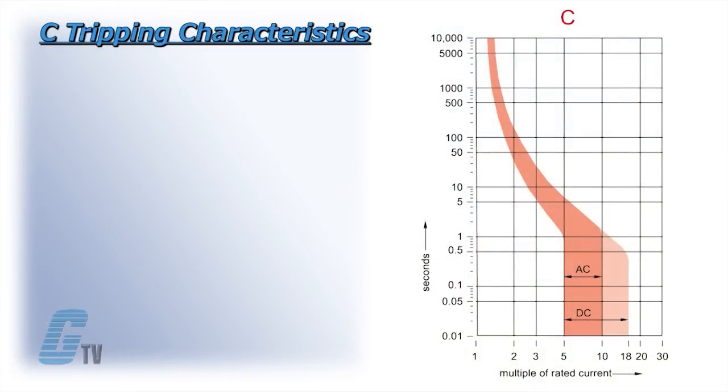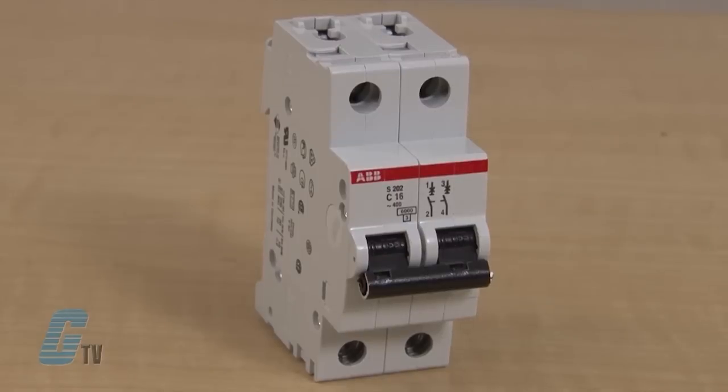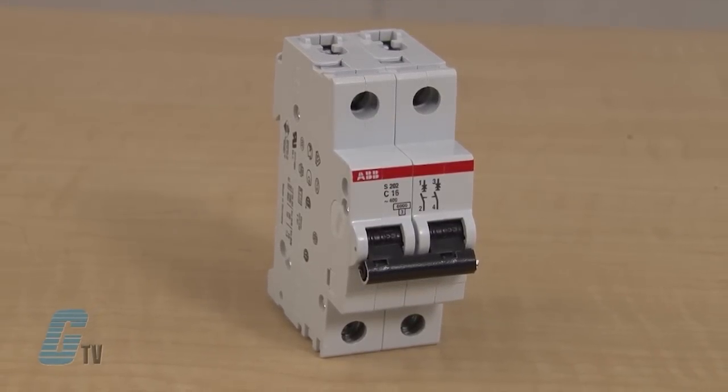The C tripping characteristic has rated currents up through 63 amps. The C time current curve is designed for medium magnetic start-up currents. Instantaneous tripping occurs between 5 and 10 times rated current in 50 or 60 Hz systems. The C characteristic is also available in other S2 series miniature circuit breakers.